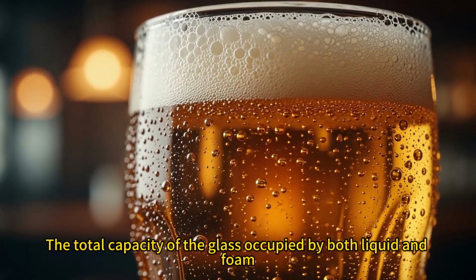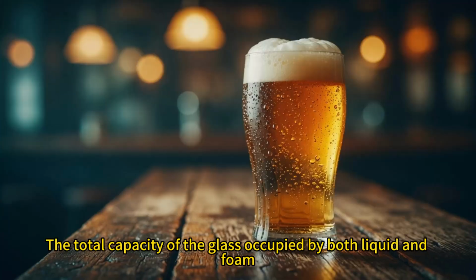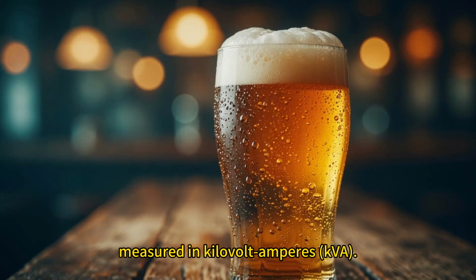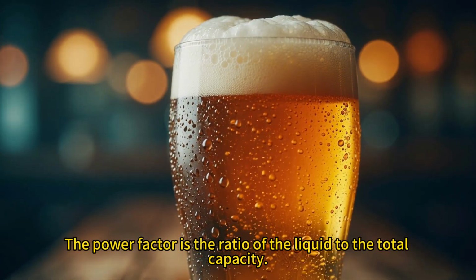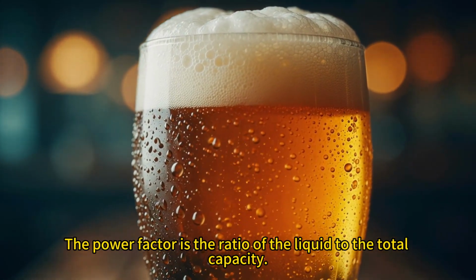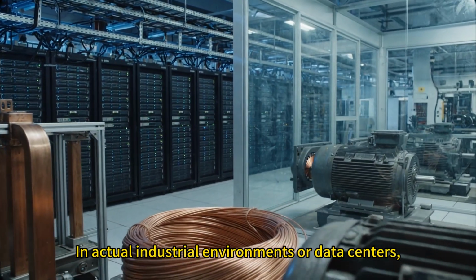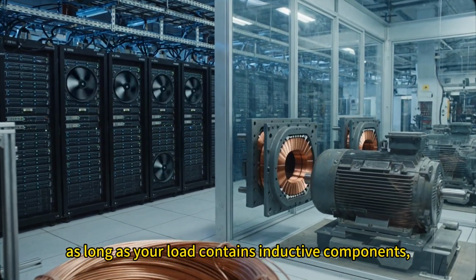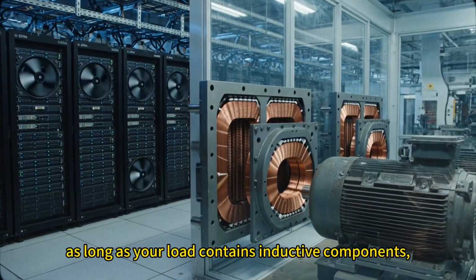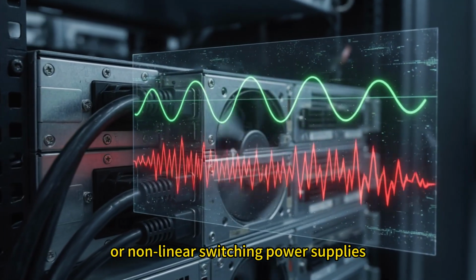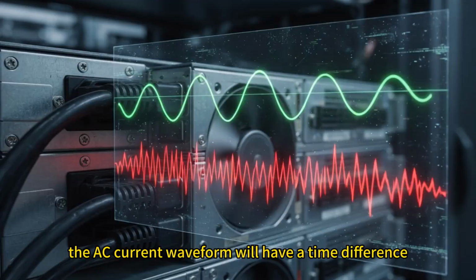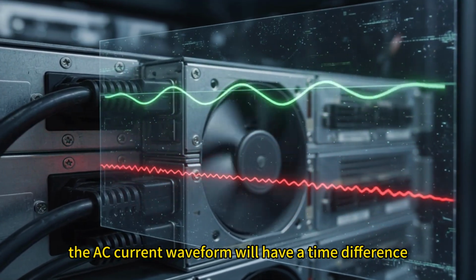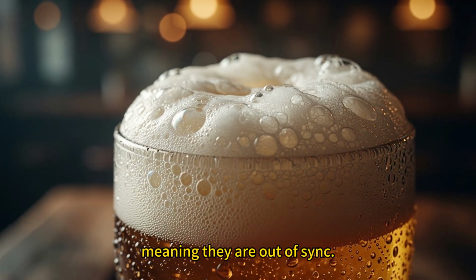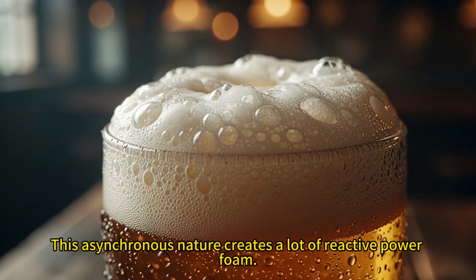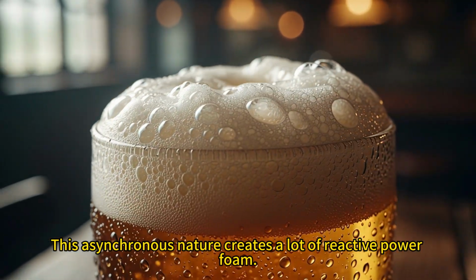The total capacity of the glass occupied by both liquid and foam is called apparent power, measured in kilovolt-amperes, kVA. The power factor is the ratio of the liquid to the total capacity. In actual industrial environments or data centers, as long as your load contains inductive components or non-linear switching power supplies, like those used in servers, the AC current waveform will have a time difference from the voltage waveform, meaning they are out of sync. This asynchronous nature creates a lot of reactive power foam.